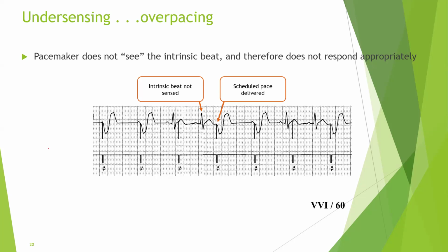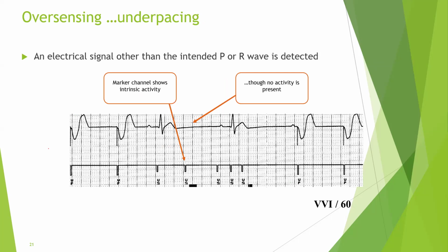Well, most of the time, this type of loss of sensing is due to micro dislodgement of the lead. Because you can see clearly it is capable of pacing. So this means that it is still attached or connected to the myocardium, but there is micro dislodgement. The tip is still on the myocardium, but the ring moved slightly away from the myocardium, and because of that, the sensitivity becomes low. On the other hand, oversensing, underpacing.